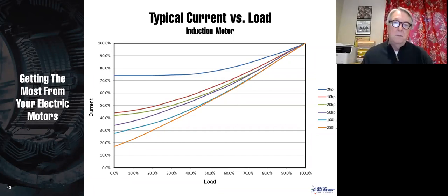When you get into much bigger motors, 10, 20, 30, 40, starting current is generally around 30%. I've got one here that actually was down about 17%, but that's really unusual. Even for very large motors, you generally would assume that if the motor is at no load, it is still pulling about 30% current. And by the way, that 30% current is just magnetization current. It's very low power factor, and it is just keeping the iron magnetized. And then as you begin to increase the load, you get more load current.